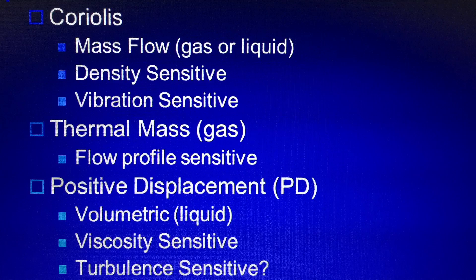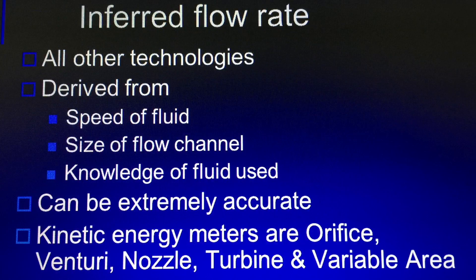Three technologies can measure primary direct mass or volumetric flow. Coriolis meters and thermal mass meters can measure mass flow directly. Positive displacement devices, such as geared meters and gear pumps, make primary volumetric flow rate measurements. All other flow measurement technologies measure flow rate by an inferred method. The flow rate calculated is derived from the speed of the fluid, size of the flow channel, and knowledge of the fluid used.